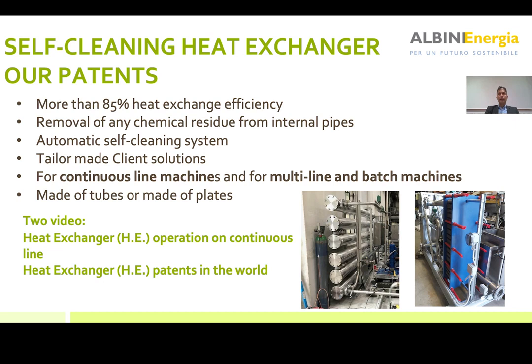One of the problems with heat exchangers in the textile field, at least, is that the chemicals contained in the wastewater deposit themselves on the walls of the heat exchanger, on the pipes and on the plates. The efficiency drops very soon, and after a couple of months your system efficiency drops to 50-60%, costing a lot of money and working hours to stop everything and clean it up.